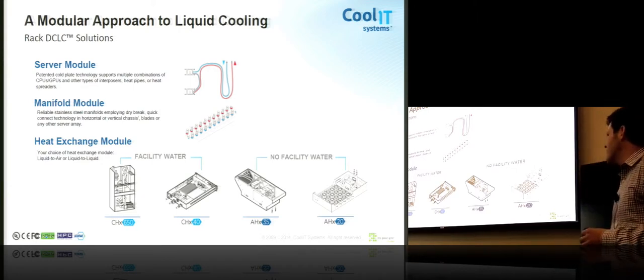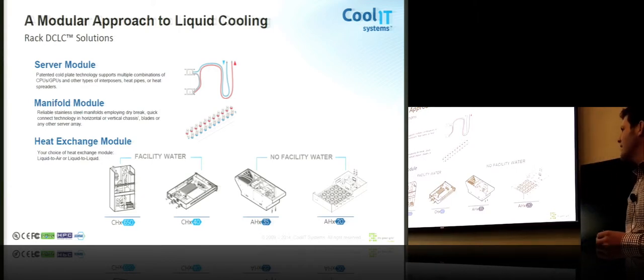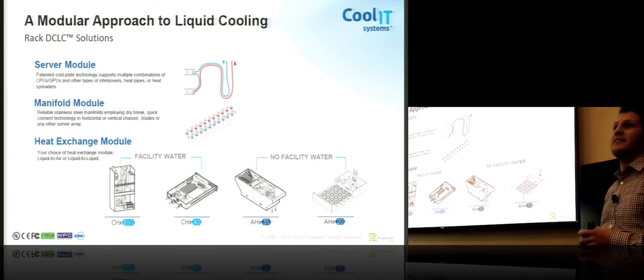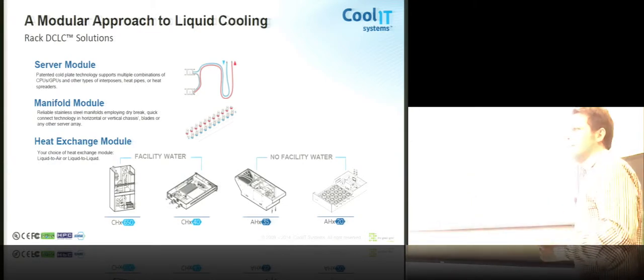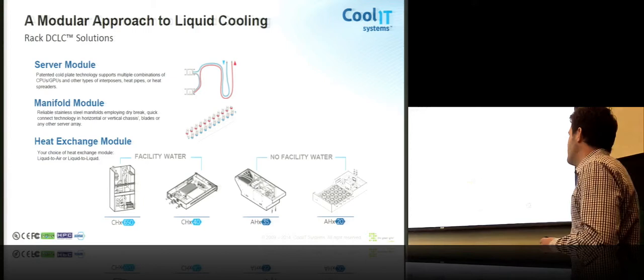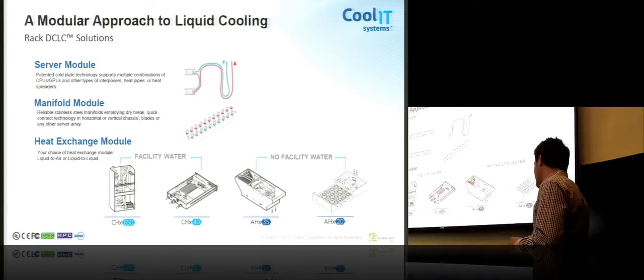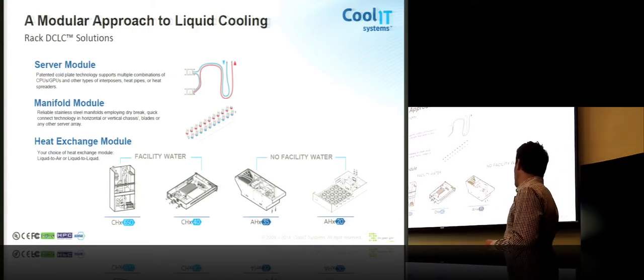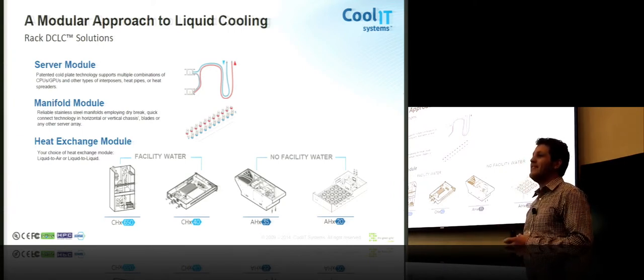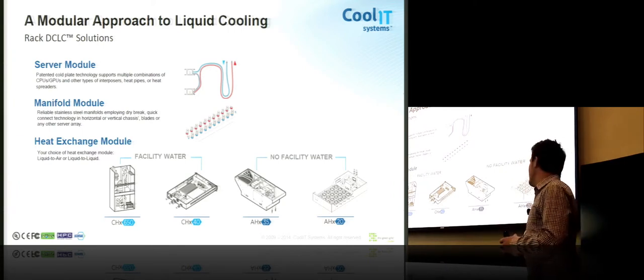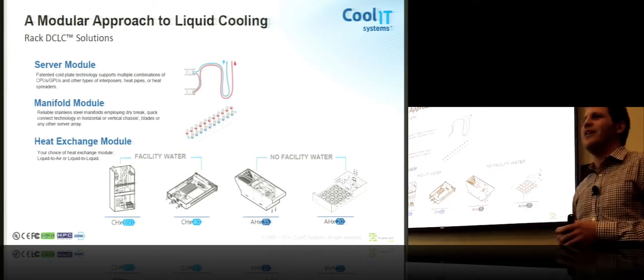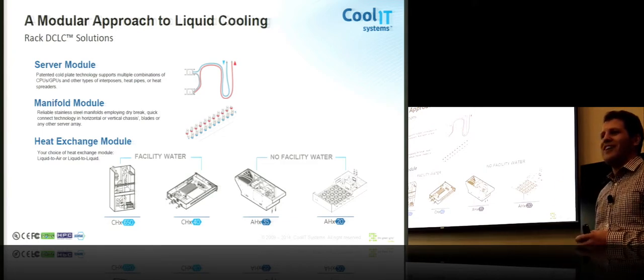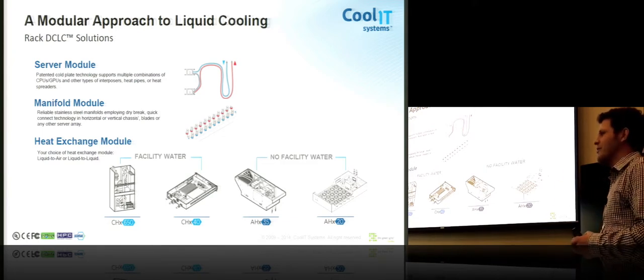On the left you have our CHX, our coolant heat exchanger line of products. And these are for when you can bring facility water or at least plumbing onto the data center floor. Whether it's above the racks or below the racks, it does require a liquid-to-liquid heat exchanger, so plumbing onto the white space. If you do not want to bring liquid onto the white space, but you still want to take advantage of the performance and density that liquid cooling allows, we do have our AHX line of products, and these evacuate that load back into the data center room.